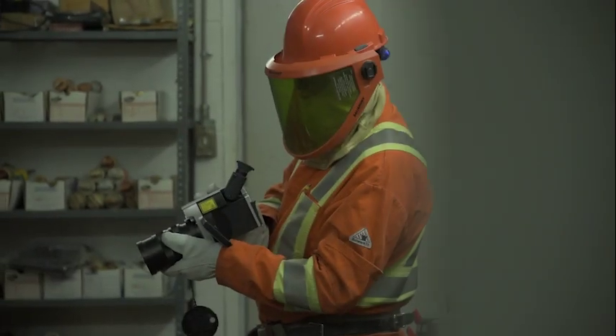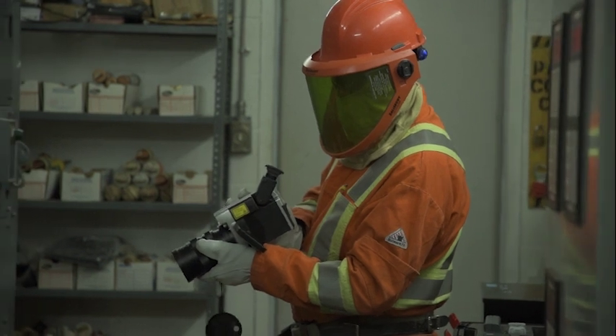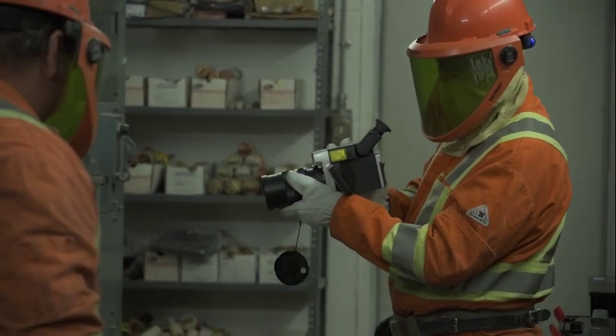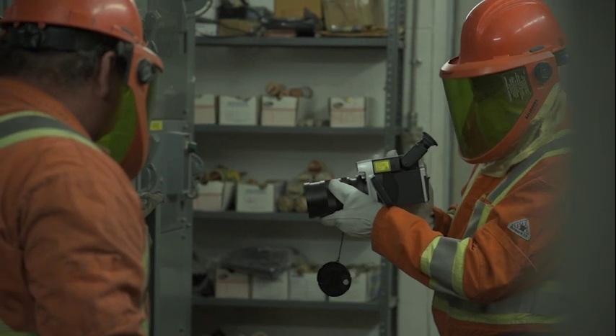Another aspect of our condition monitoring is ultraviolet imaging. In doing this, we're looking for what's called corona discharge. Corona discharge is strictly a chemical reaction brought on by high electrical stress in combination with poor air quality. Really what it is, is the electrical breakdown of air. But the side effects from it are quite phenomenal. We've got ozone, we've got ultraviolet, we've got carbon.